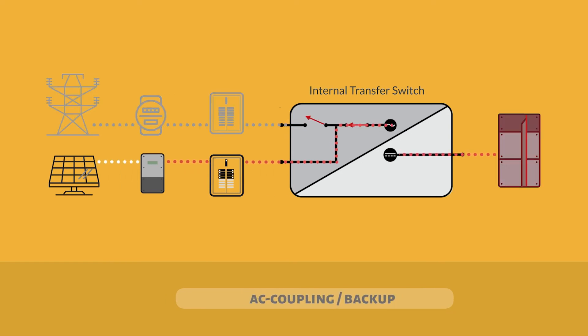In the event of a power outage, the hybrid battery-based inverter will open its AC input relay, isolating the grid and immediately begin inverting from the batteries, providing backup power to the protected loads panel. And since the grid-tied inverter is coupled with the output of the hybrid battery-based inverter via the protected loads panel, it will think the grid just had a slight interruption and begin its five-minute source verification. Once qualified, the grid-tied inverter will begin augmenting the inverted battery power with solar energy.